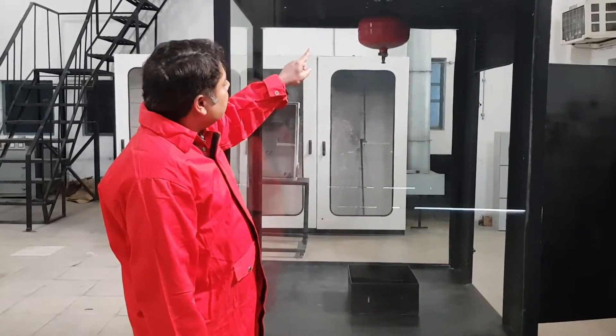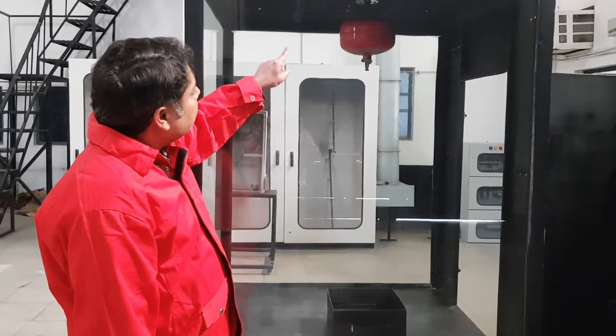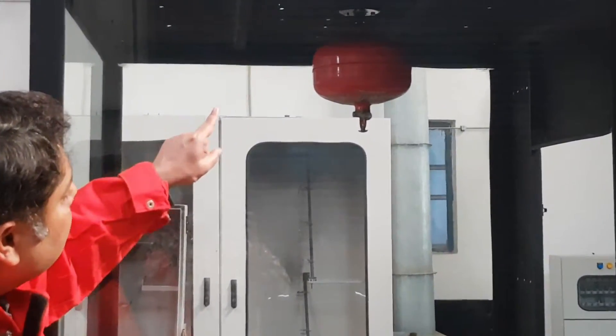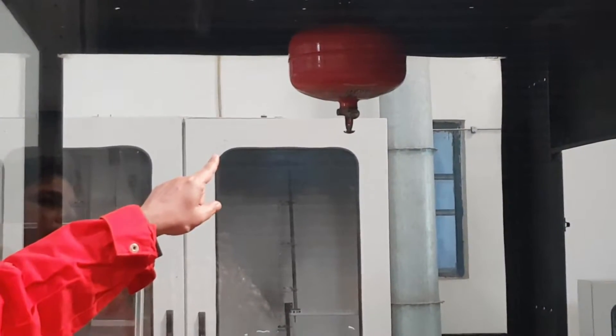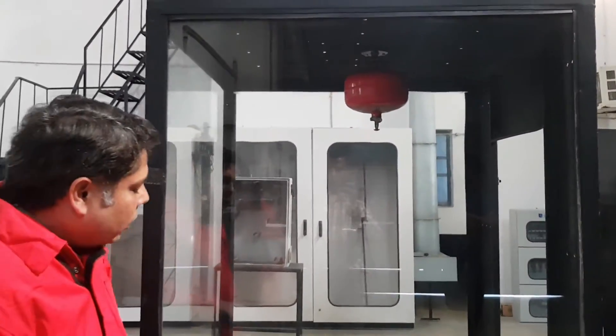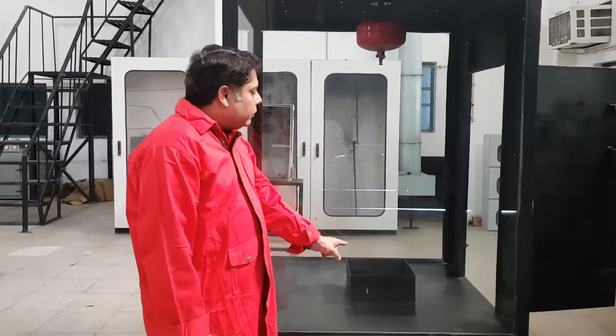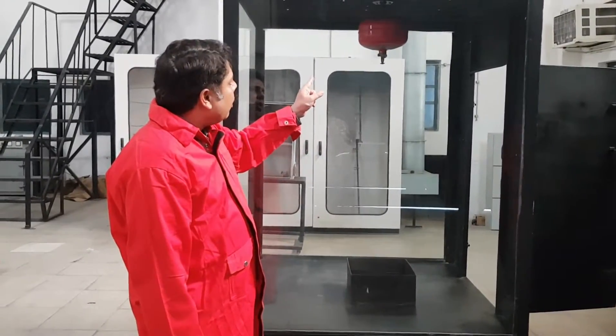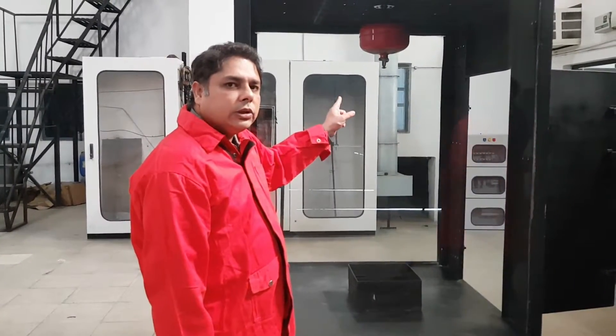As you can see, the cylinder has been placed vertically with its base plate on the ceiling, installed with a fastener, and the nozzle or sprinkler is at the bottom. The pressure in the cylinder is 10 bar. For the purpose of demonstration, we are going to pour 1 liter of Heptane into the container at the bottom. We will let the fire grow, and as the temperature reaches 68 degrees at the tip of this sprinkler, the extinguisher will activate and extinguish the fire.